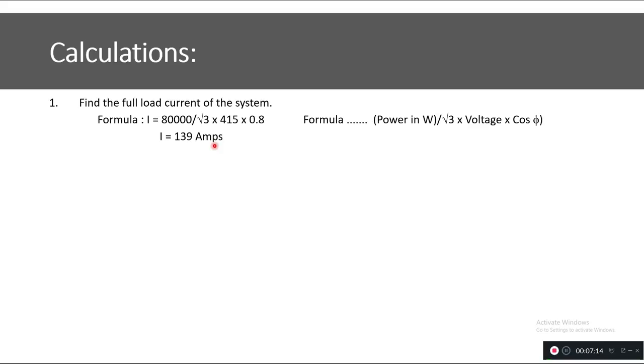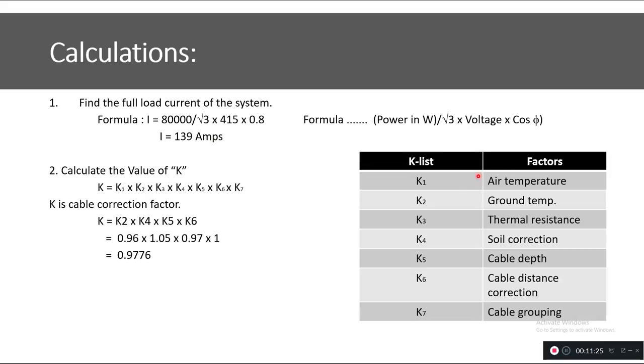However, atmospheric and meteorological factors cause increases or decreases in the current carrying capacity of the cable. So the next step is to calculate the correction factor K. K represents the combined correction factor for the cable based on atmospheric conditions and the cable laying methodology. You can see on screen the list of factors included in K, from K1 to K7.